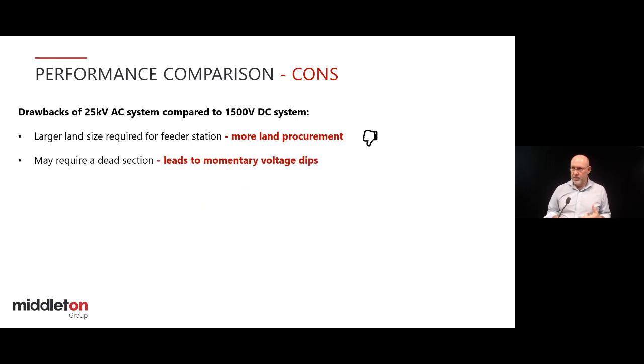Stephen mentioned neutral sections. In the traditional 25 kV system, you've got an out of phase issue with transformers. That means there's actually a little bit of dead section in the overhead where the train has to run through. More maintenance. It doesn't really affect train operations as long as you put your neutral sections in the right place. Like, you wouldn't put your neutral section right at a signal. That would be rather crazy. So as long as the system's designed properly, it's not an issue.